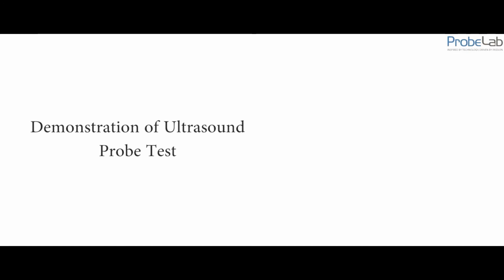Okay, I'm going to be demonstrating for you a quick test that you can do on your ultrasound machine to test for the quality of the probe. This test in no way is going to replace a full acoustic spectrometry test of the probe. That's typically done by either biomedical or a biomedical physicist in medicine.